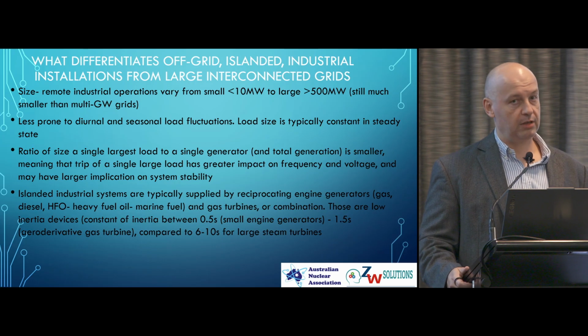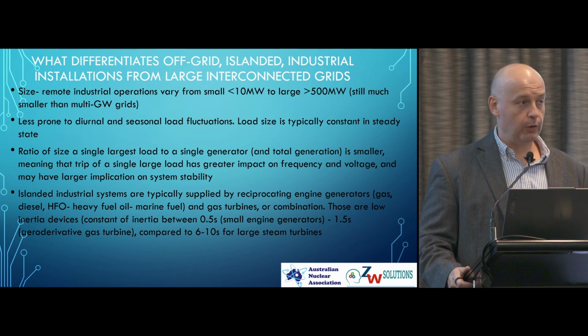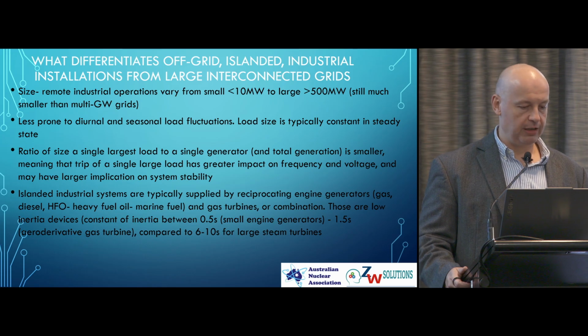Currently, based on my experience and based on locations, remote sites are typically supplied by diesel generation or heavy fuel oil engine and turbine generators. That's the majority of them. Those are typically smaller machines in the range of 1 to 10, 20 megawatts. They don't have much inertia, so they're pretty weak, so to speak.